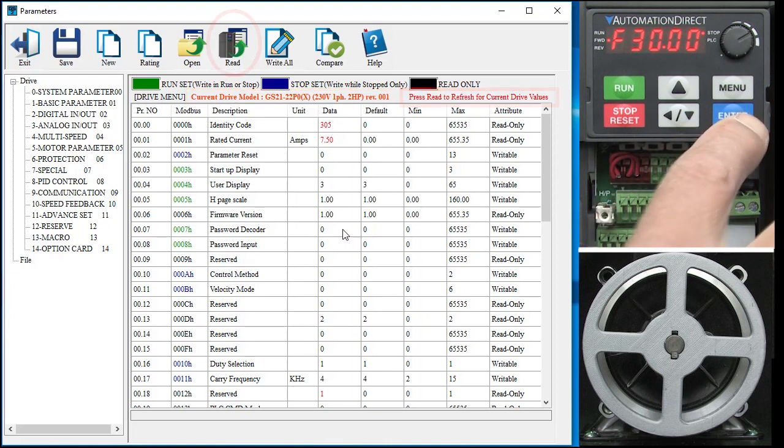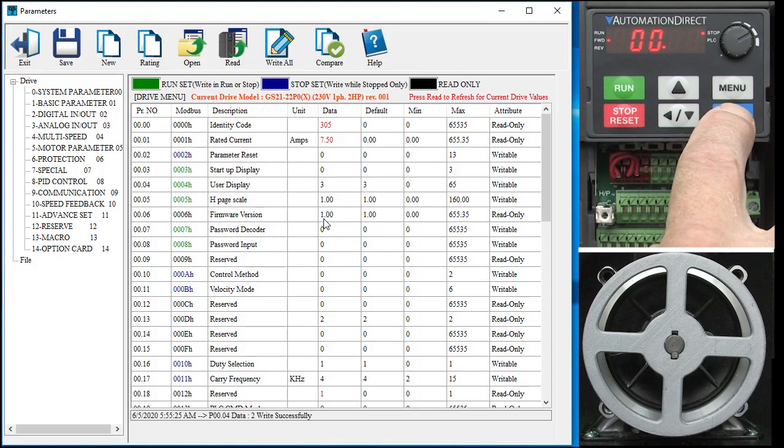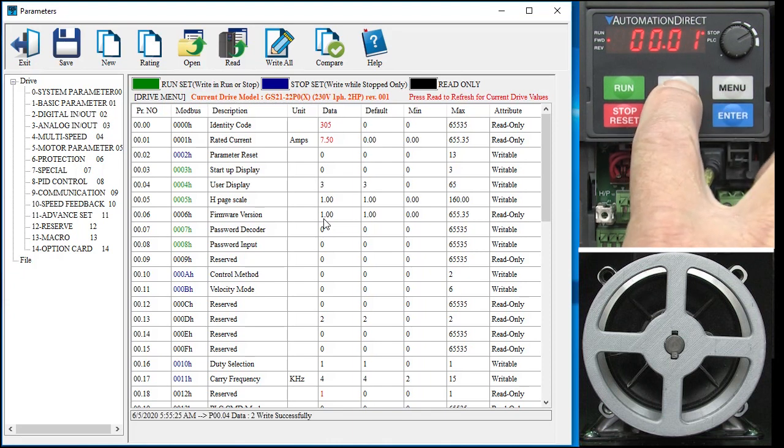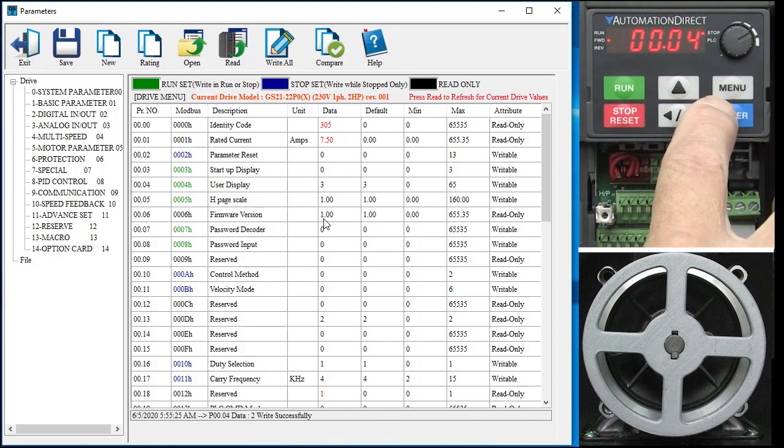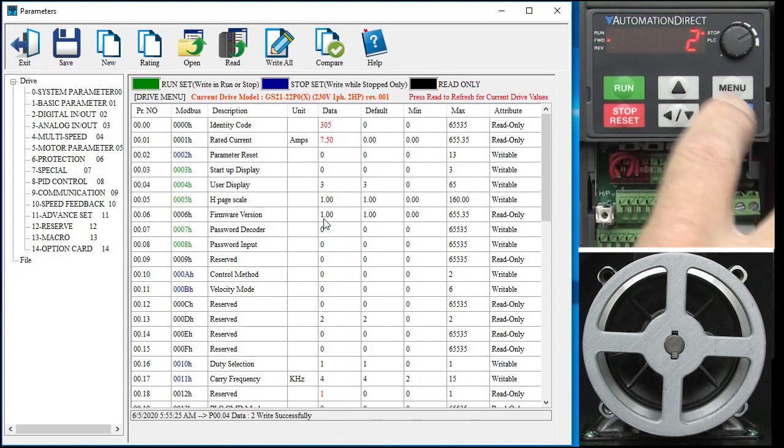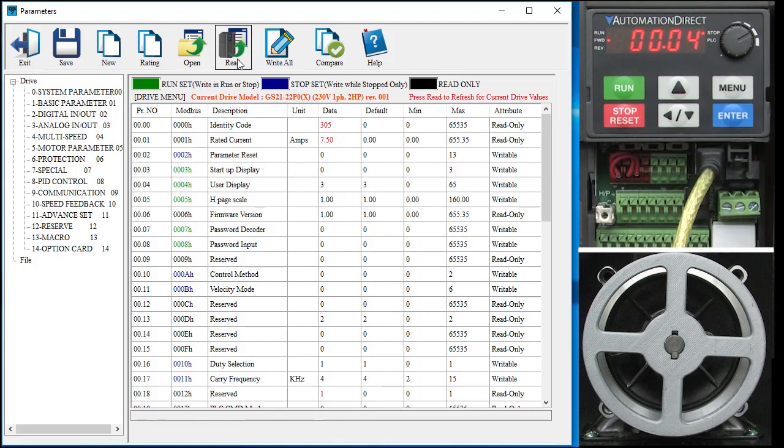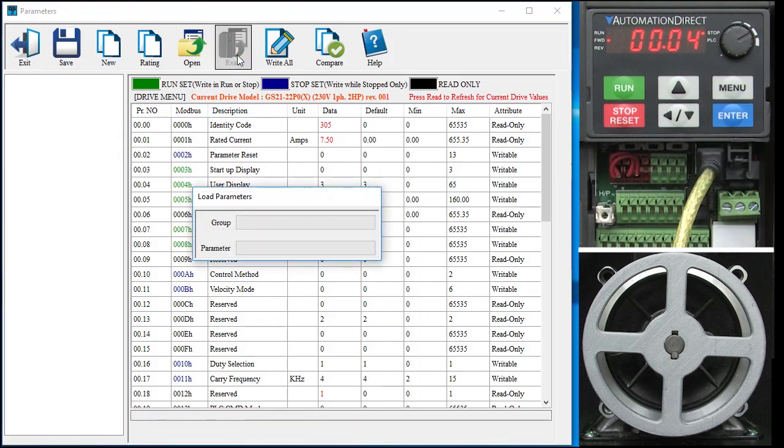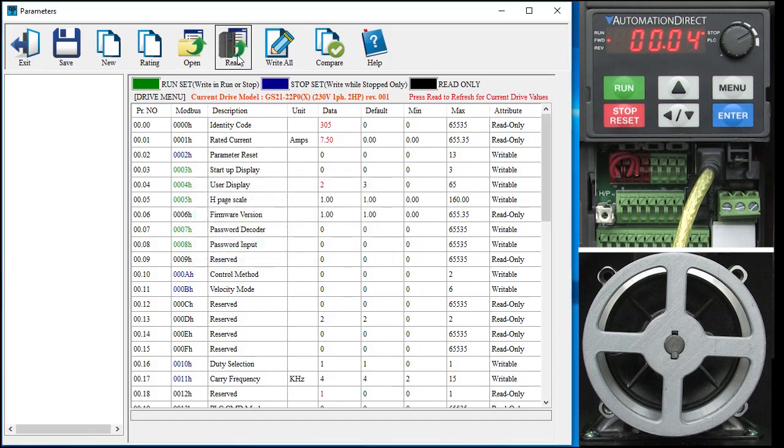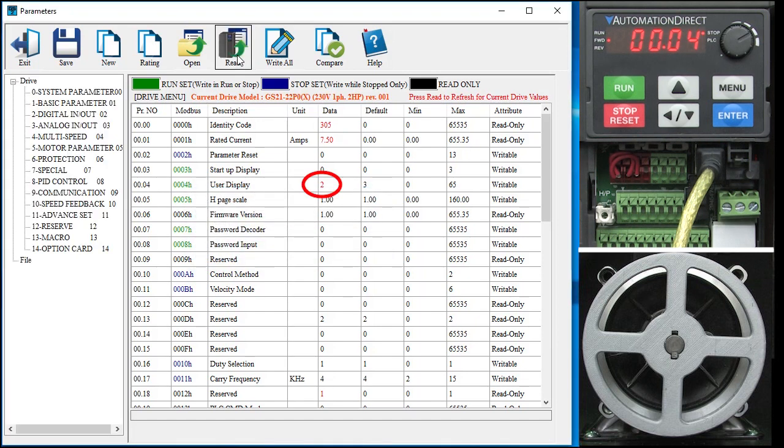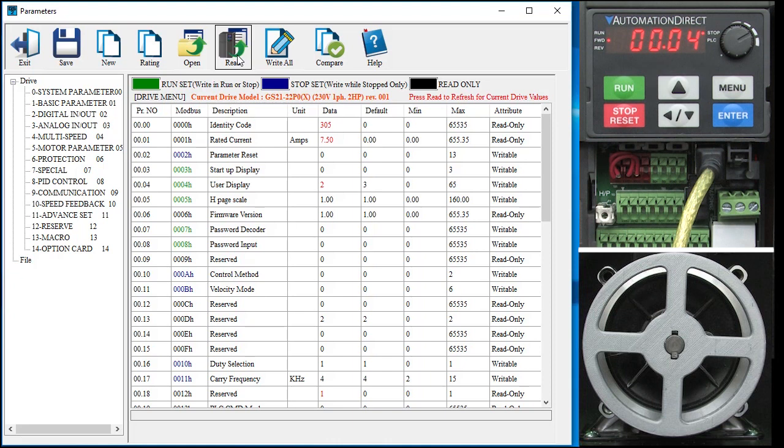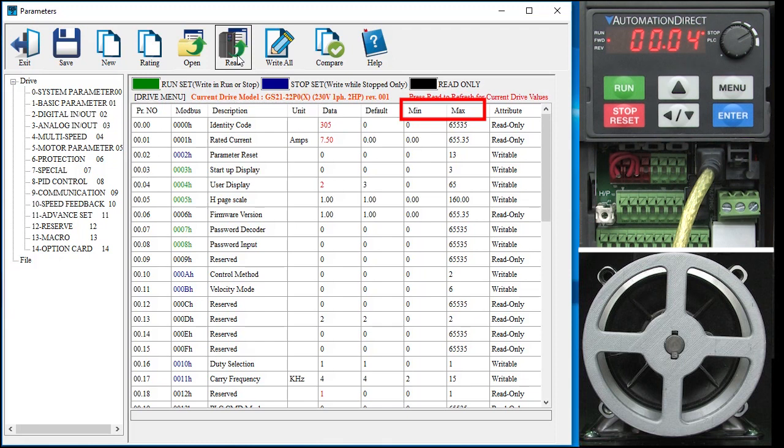If I reach over to the drive and change parameter 0.04 to a 2 and hit read, give it a few seconds, sure enough we see the new parameter. It is red because it is not a default value. I love that I can quickly see what is different just by looking for the red parameters. You can also see what the min and max allowable values are for each parameter.